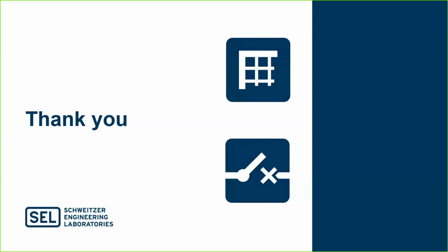Now, there may be some people listening thinking, oh man, I really need it not to do that. So hear me out here. If you have a COM failure with a recloser or switch or even a breaker on a feeder that FLISR is operating on, the safest thing to do is block on just that feeder. Other feeders can stay armed and operational, and they can work with each other. But we automatically disarm or block on that feeder as long as communications are gone. That's how it is right now.